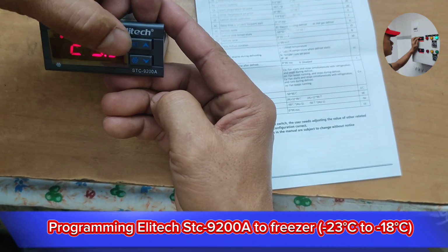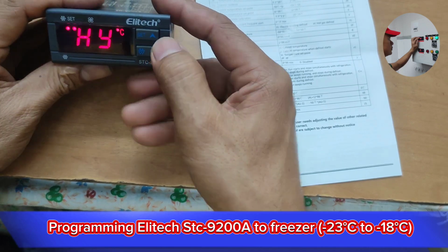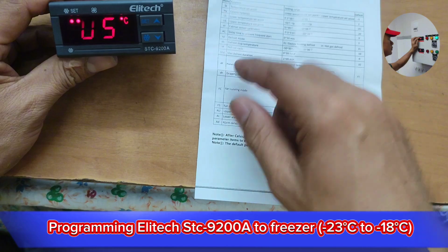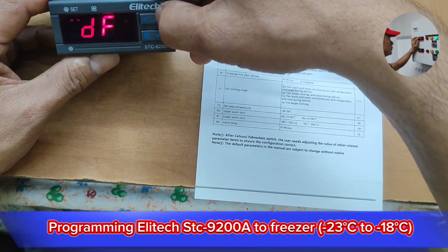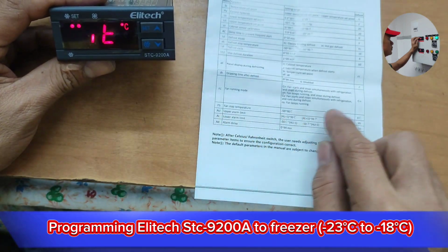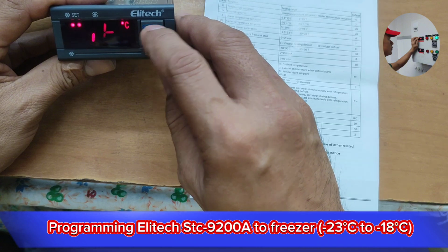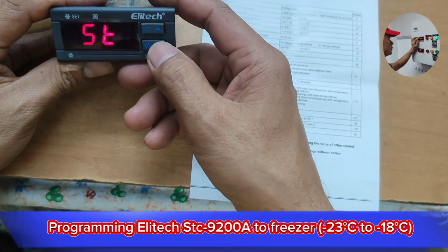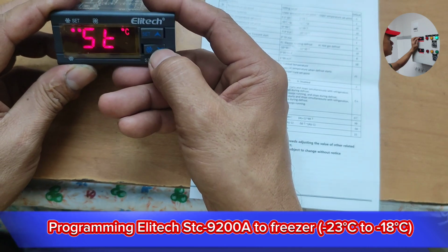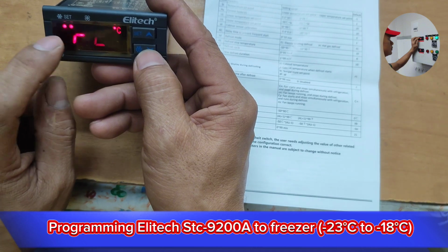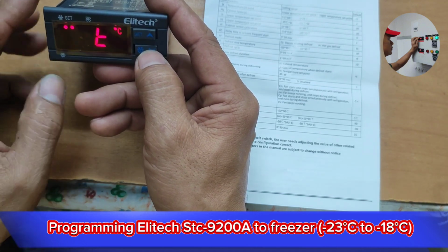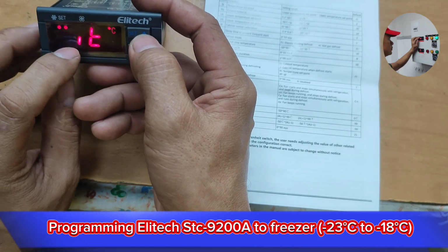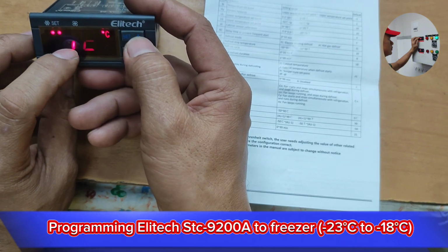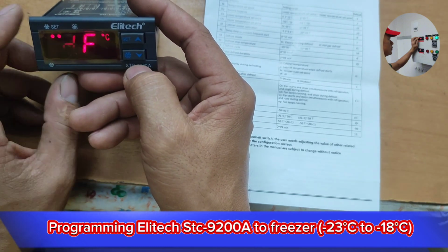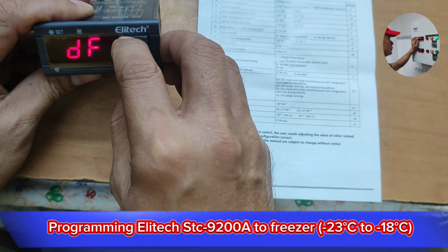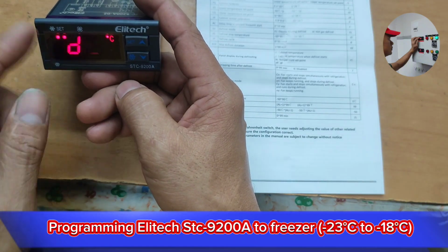Let's enter the programming again by pressing the set and add-on button. And let's proceed to DF. Preset. And the default is RT, but we're going to select DF here. Set point: when the defrost happens, my set point is negative 23, this will show up. RT, cabinet temperature, it shows the real temperature of the cabinet during defrost. IT, this is the cabinet temperature when defrost starts. And let's select DF. This is the best for me, because when it defrosts, DF appears, meaning defrost.